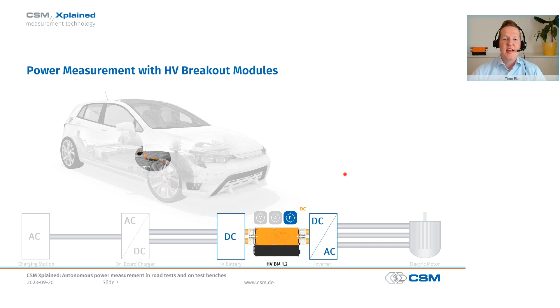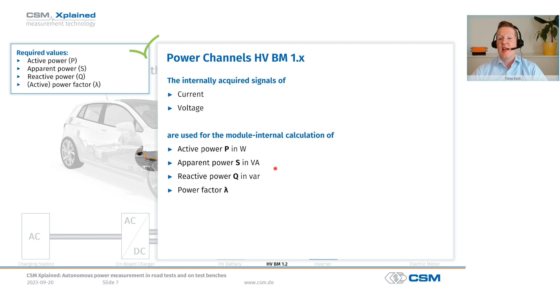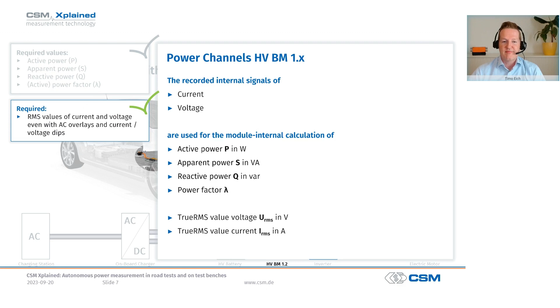For this purpose, the HVBM takes the measured signals of current and voltage and calculates on board and in real time the active, the reactive, the apparent power, as well as the power factor. In addition, the HVBM calculates the RMS values of voltage and current. For all of those calculations, no additional computing instance is needed. The HVBM calculates all those important values completely autonomously. And we have then already fulfilled two of the requirements of our customers. If you remember the required power characteristic values here on the upper box and the RMS values.